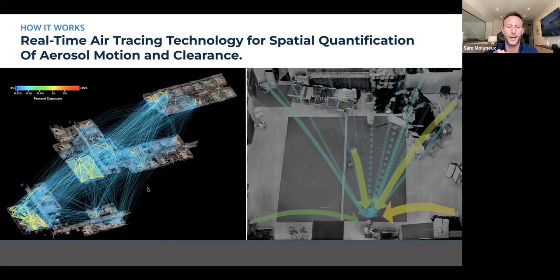The second thing that I'm looking at on the left-hand side is actually what this looks like at a building scale. Through the use of DNA tracers, where we have barcodes that are able to tag release locations and even enable us to count individual molecules or particles that are transiting through time and space in a building, we actually have a very sensitive way to measure where air goes and how fast it's cleared, even across floors. And so what you're looking at here is small within room views where you can see the local transmission paths that we discover, as well as floor to floor views.